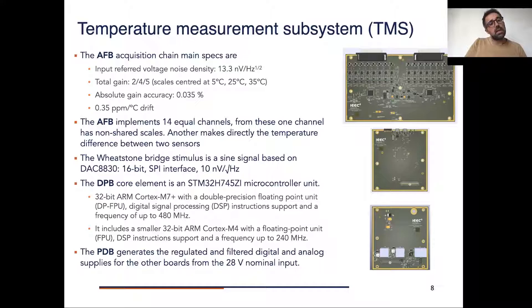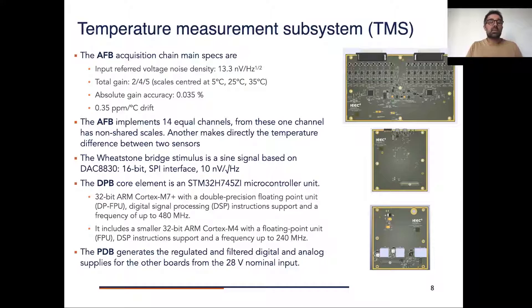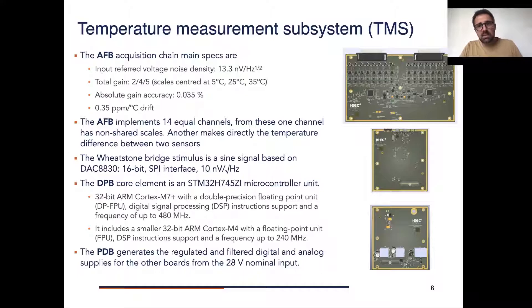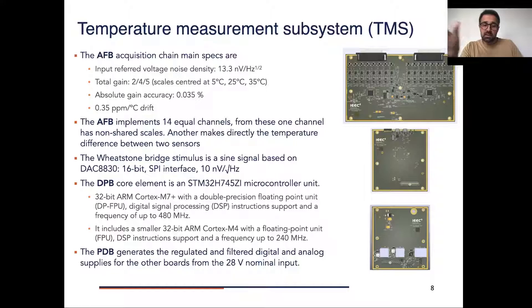The analog board basically implements a low-noise acquisition. It has three different scales and of course a very low temperature dependency, which is required for a high-sensitivity temperature measurement subsystem. It implements 14 channels, and some of them have the possibility to implement differential measurements between two sensors.